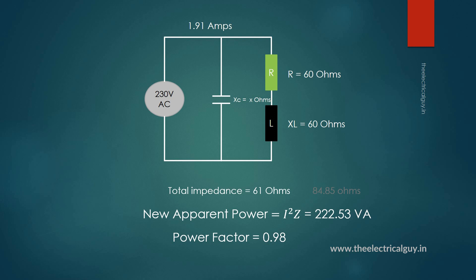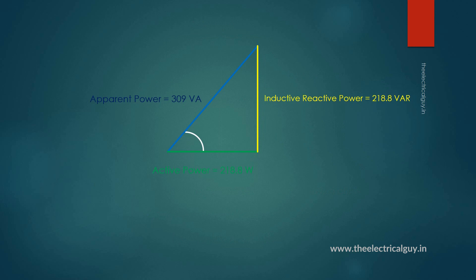So let's understand what has happened here. The power triangle shows the different types of power in the circuit without a capacitor. Here we can see the inductive reactive power is 218.8 VAR. So to improve the power factor of the circuit, we added a capacitor. The reactive power from the capacitor — let's call it X VAR — cancels out with the inductive reactive power, and the resultant power triangle shows that 218.8 VAR minus X VAR of reactive power now remains in the circuit, which has caused the improvement in power factor.